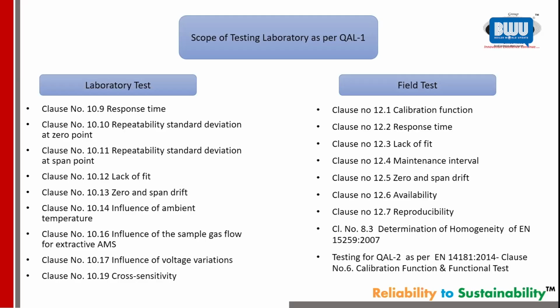So influence of gas, sample gas flow, extractive rather, not in-situ type. Influence of voltage variations, cross sensitivity. Many people say what is the need of a UPS, we don't have power cuts here, so we give direct electricity. That is also right, if power doesn't go then it is very good, but this bypasses clause 10.17. So the reliability is compromised. I don't say it is wrong, but it is compromised a little bit.